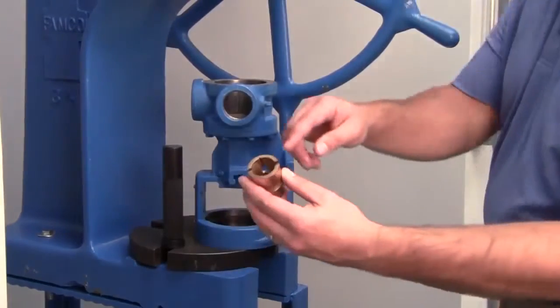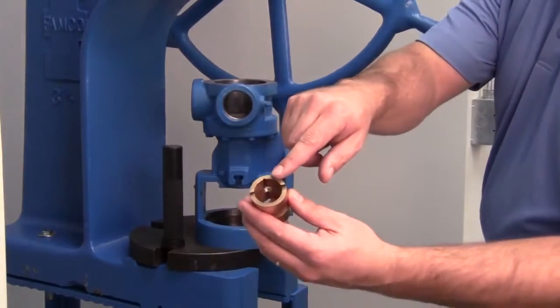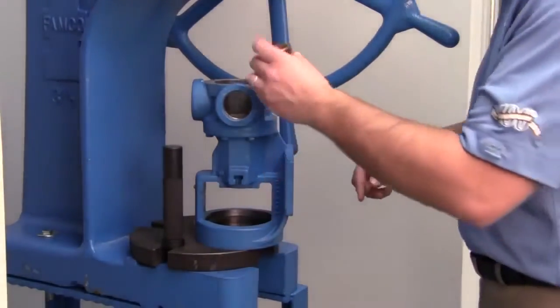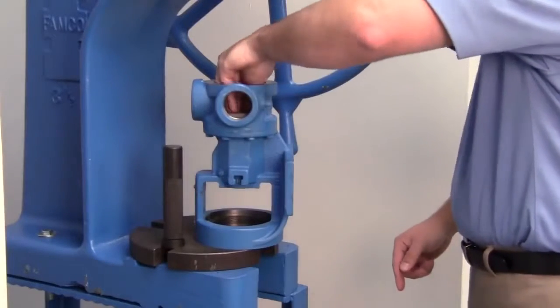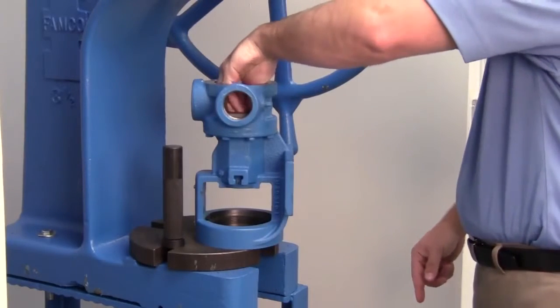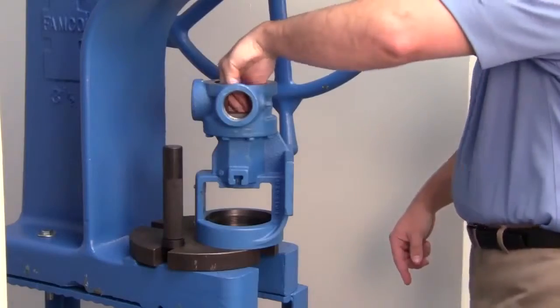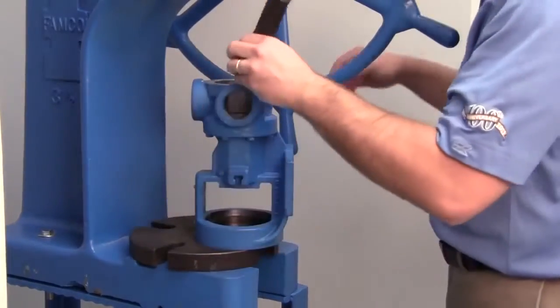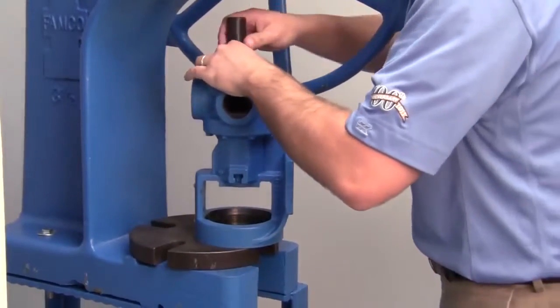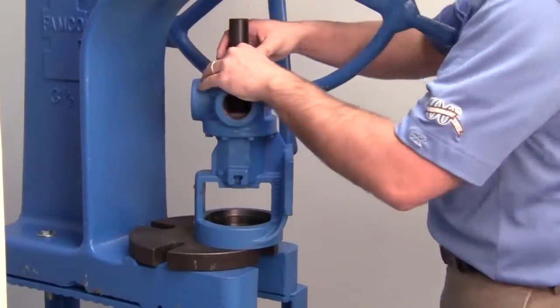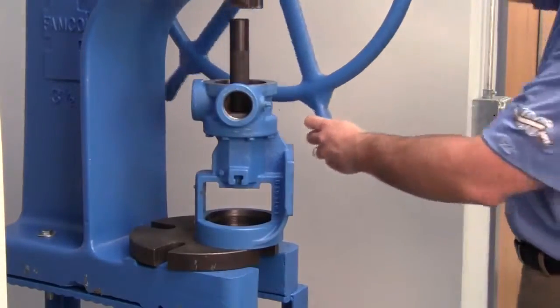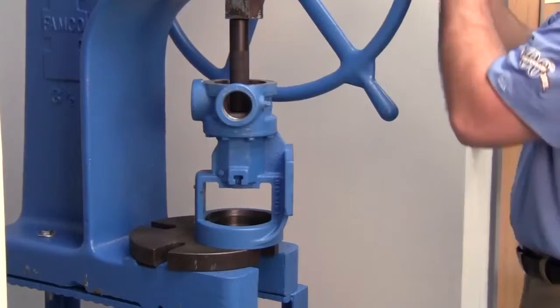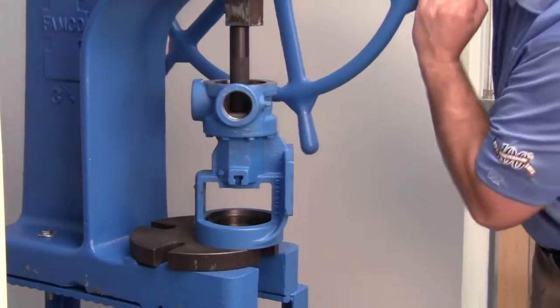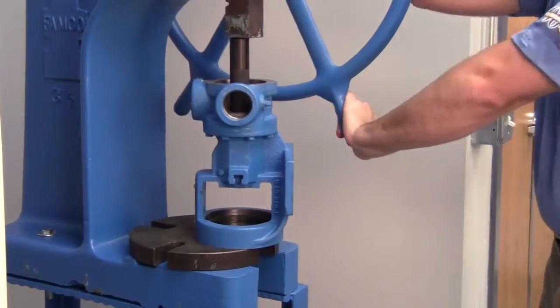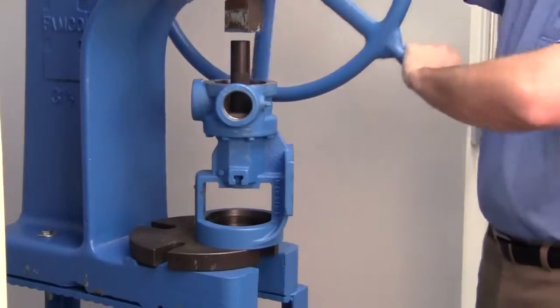Install the bushing into the bracket. Bushings with lubrication grooves should be installed with the groove at the top or 12 o'clock position. Carbon graphite bushings require extreme care to avoid breaking the bushing during installation. For carbon graphite bushings, use a lubricant and make certain that the bushing is started straight. Use a press to completely install the bushing in one continuous motion. Starting and stopping will crack the bushing. Make sure slots in the face of the bushing are towards the rotor end of the bracket.